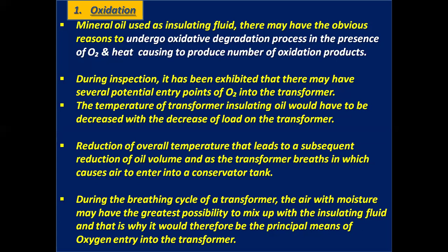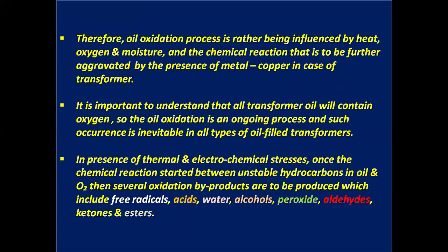During the breathing cycle of a transformer, the air with moisture has the greatest possibility to mix with the insulating fluid, and that is why it is the principal means of oxygen entry into the transformer. Therefore, the oil oxidation process is influenced by heat, oxygen, and moisture, and the chemical reaction is further aggravated by the presence of copper in the transformer. It is important to understand that all transformer oil will contain oxygen. So, oil oxidation is an ongoing process, and such occurrence is inevitable in all types of oil-filled transformers.